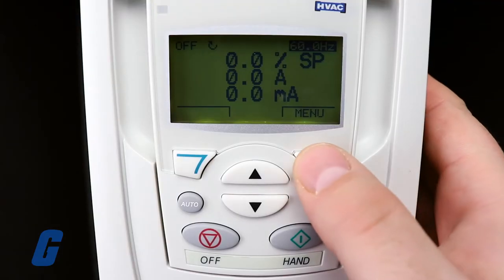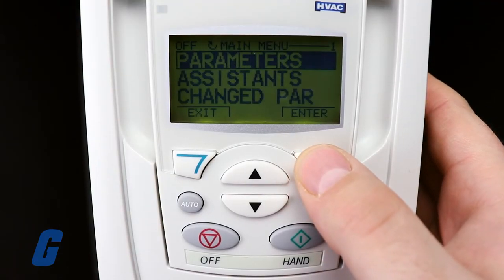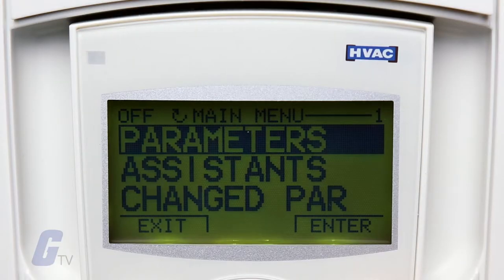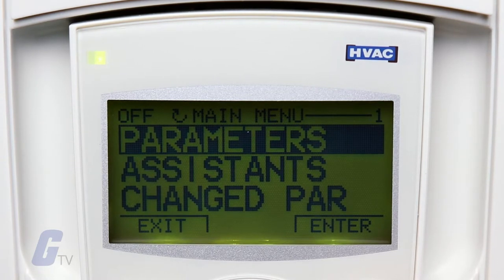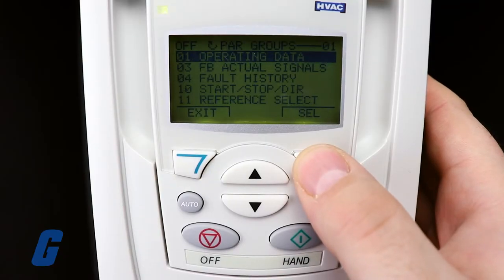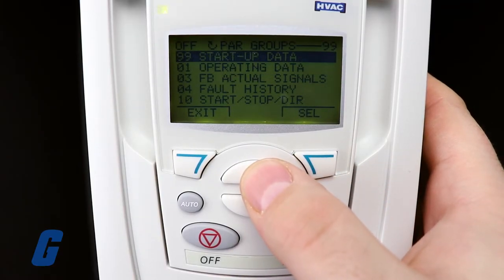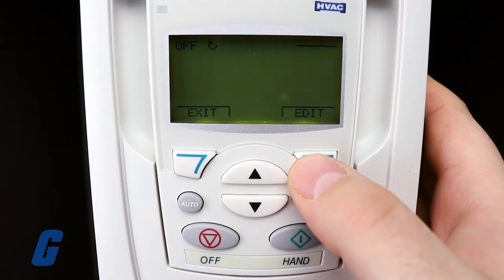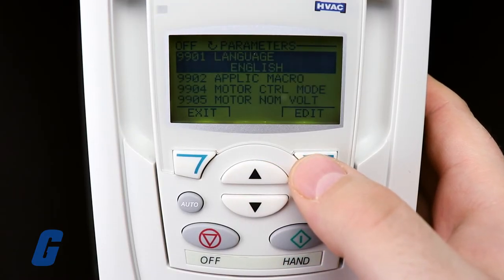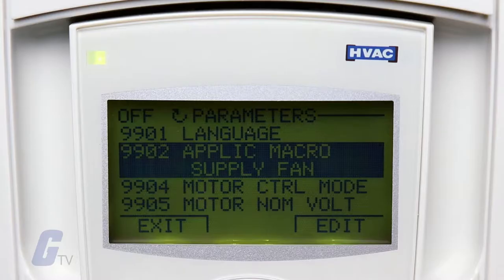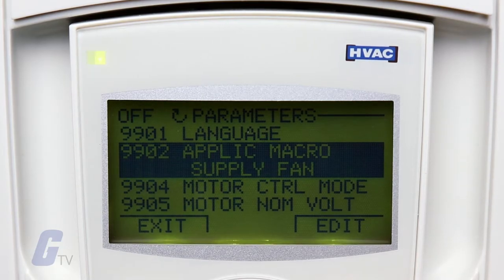press the menu button from the main menu screen to open the options menu. From here, use the up and down arrow keys to scroll to the parameters option, and then press the enter key to open it. Use the up and down keys to navigate to parameter 9902, which is the application macro parameter.